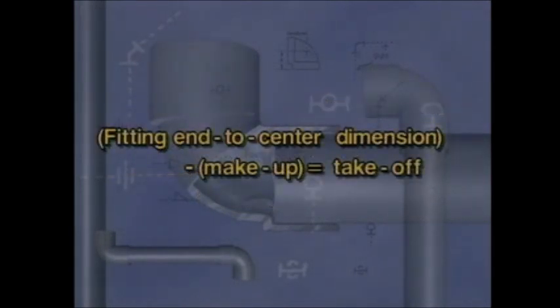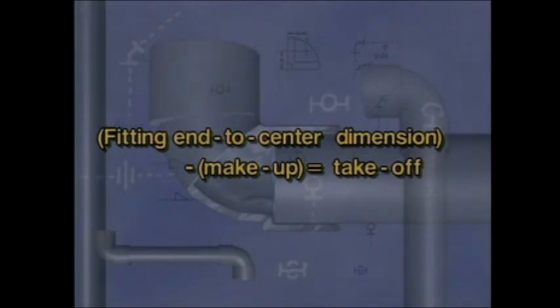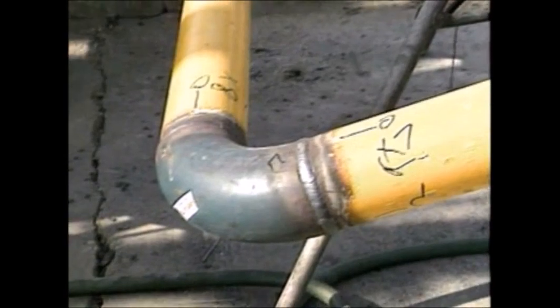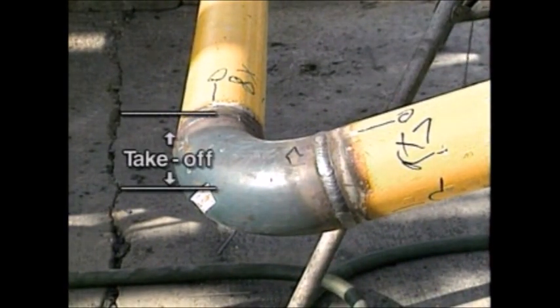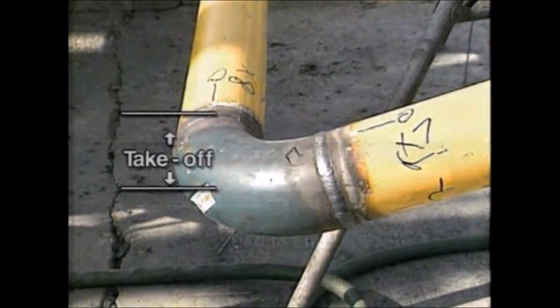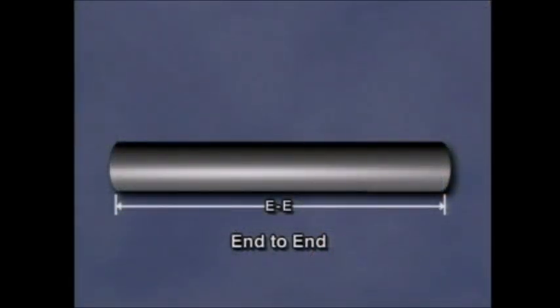Again, to figure takeoff, find the end-to-center dimension for a fitting from the table. Then subtract the make-up, or how far the pipe inserts into the fitting. For socket weld fittings, include the allowance for heat expansion. For butt weld fittings, no make-up is involved, so takeoff is the dimension from the end to the center of the fitting. Of course, if the dimension is end to end, that means the actual pipe measurement and takeoff doesn't have to be figured.